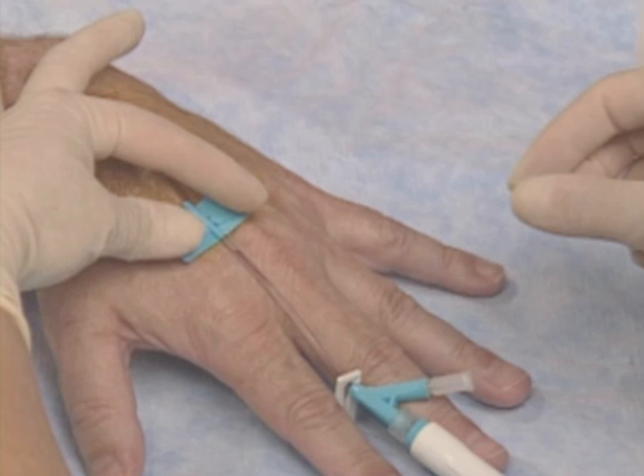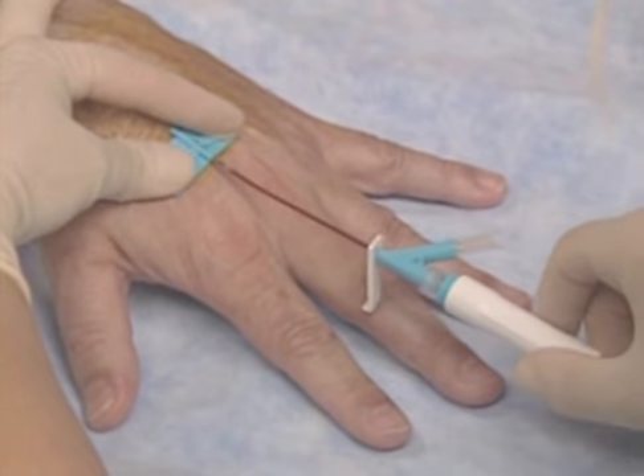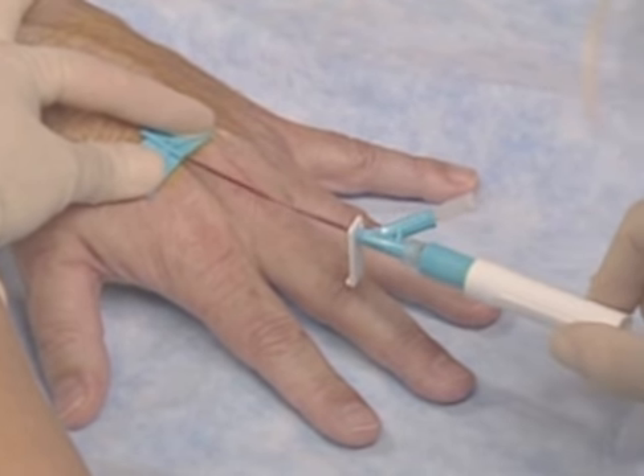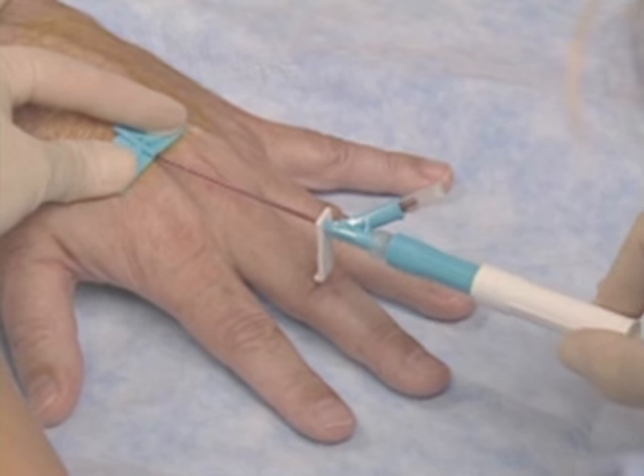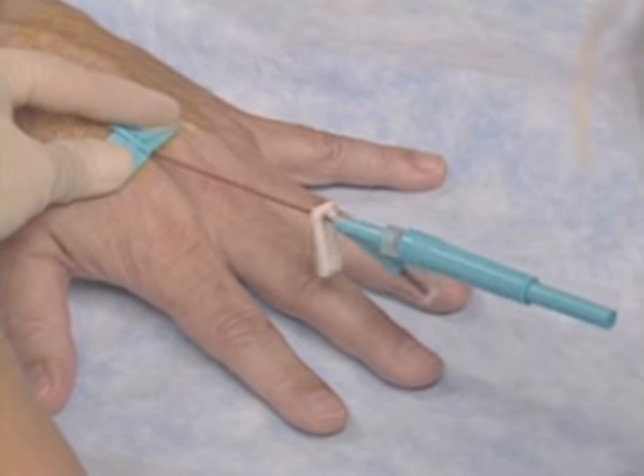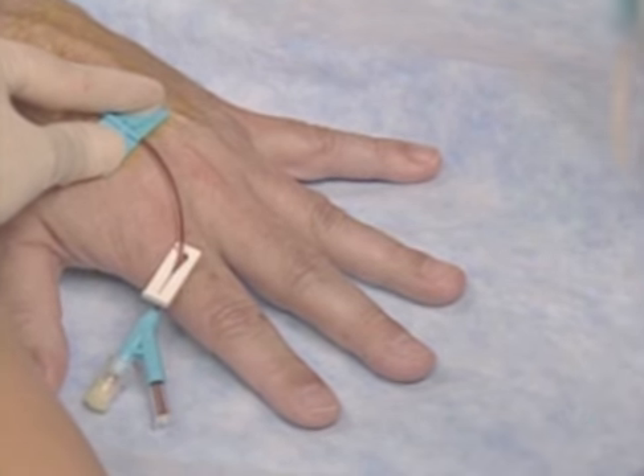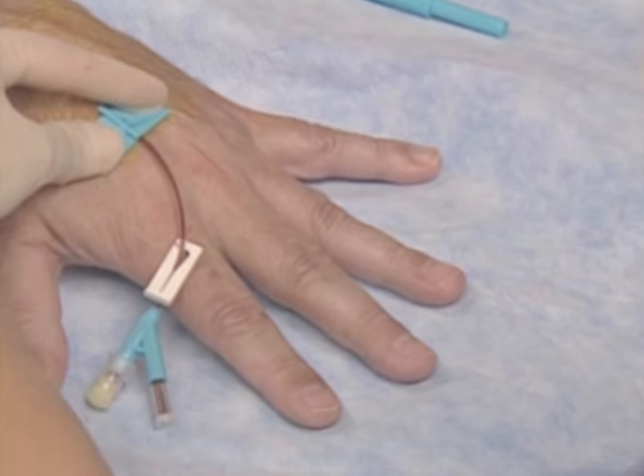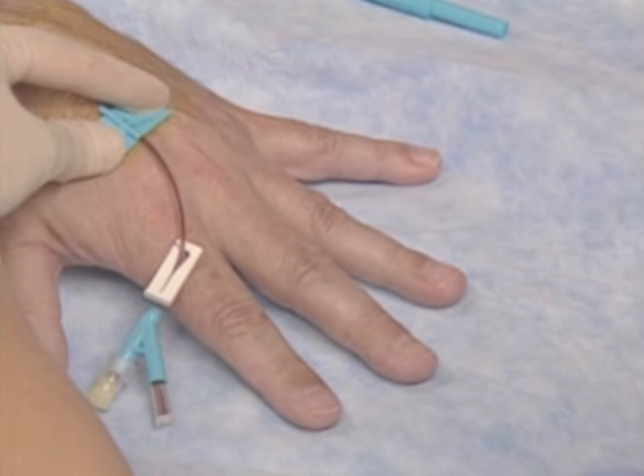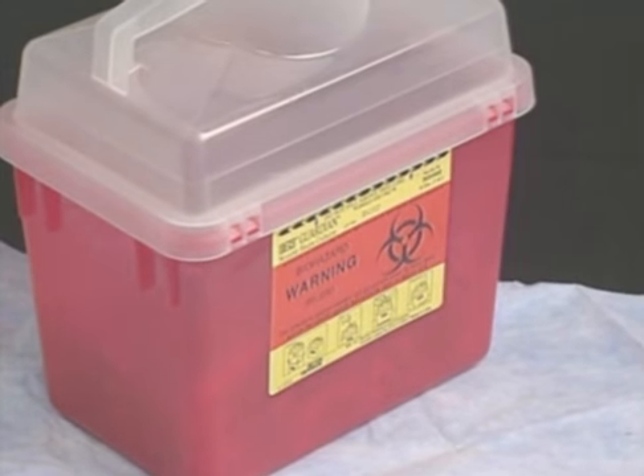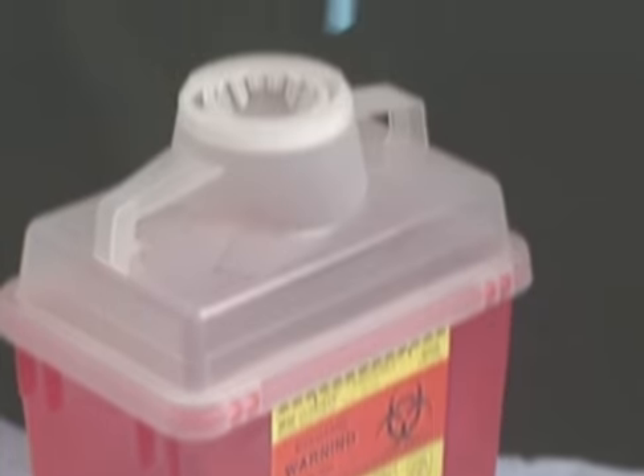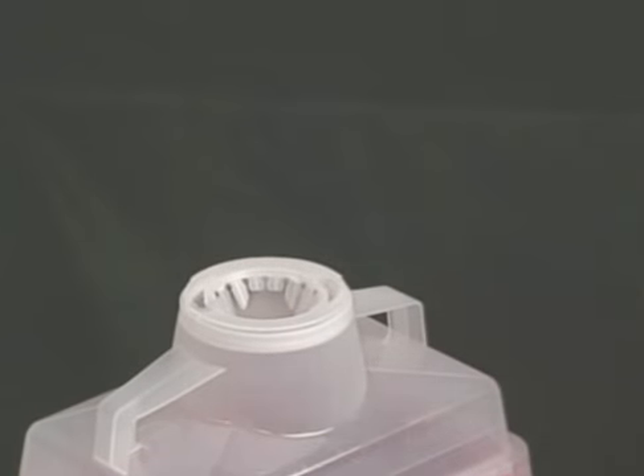Keeping the extension tubing straight, grasp the pebbled area firmly on the safety shield and pull back in one continuous motion. As the shield telescopes and releases, it passively encases the needle into the safety shield. At first, this might feel awkward. Keep practicing until you're comfortable with the continuous motion. The shielded needle should be disposed of into a puncture-resistant, leak-proof biohazard sharps container.